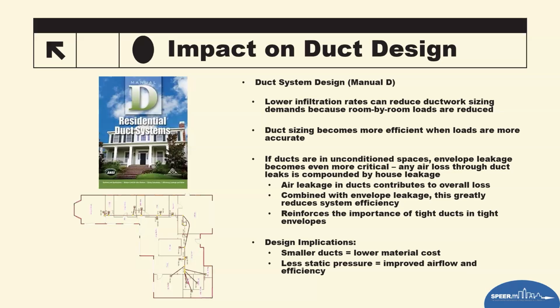So if we have older HVAC contractors on here, we just talked about a second ago basically how they used to size it: oversize the system, undersize the ducts. Also, what happened with that is, if you had in-field duct board transitions or Ys being built, that stuff would just blow itself apart eventually, and then you would leak a ton to 2.5 tons of air in the attic, and that's detrimental to the homeowner as well. So adding duct leakage on top of that is horrible. So there's a problem with all of that.